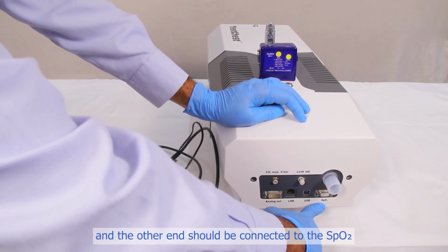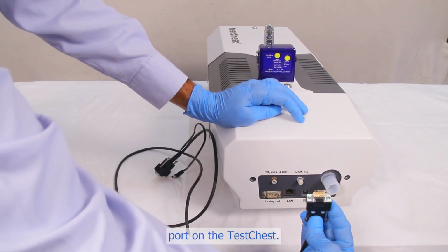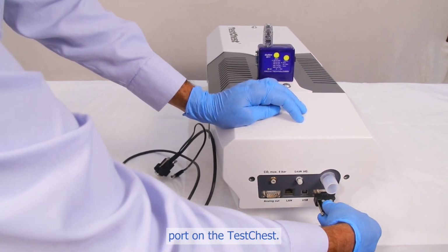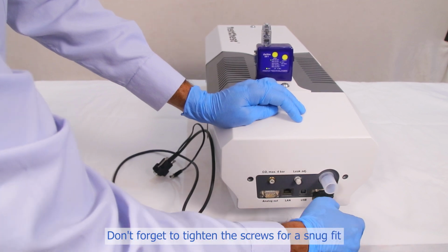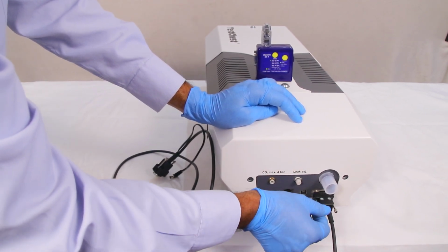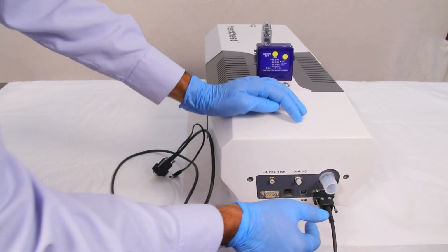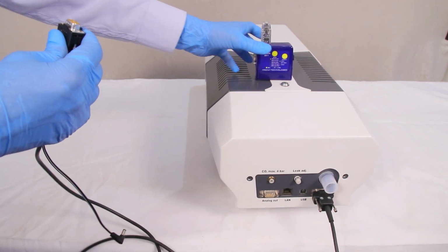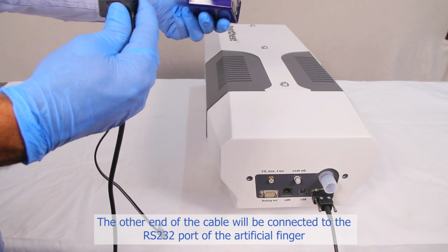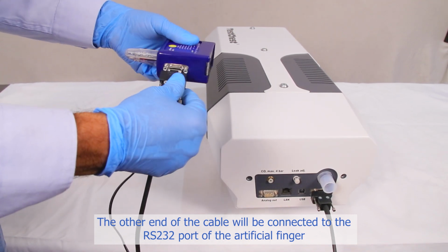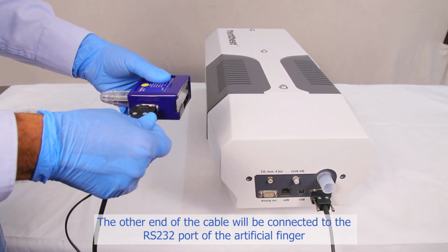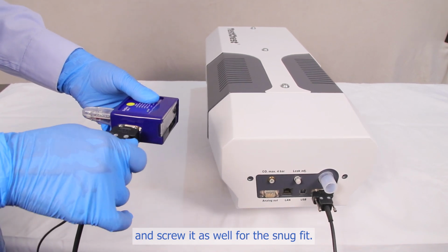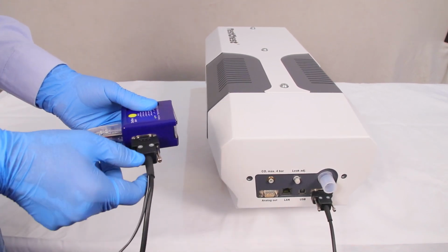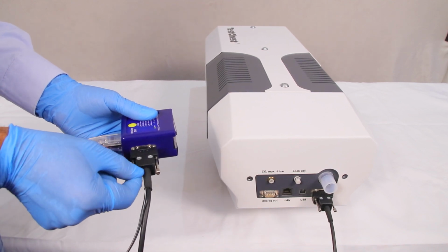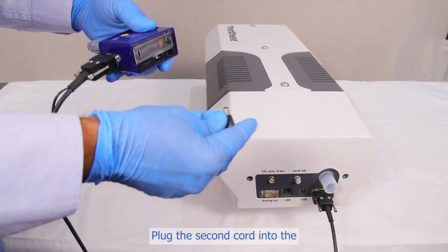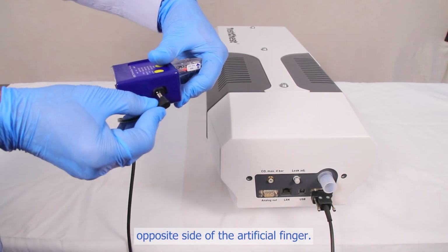And the other end should be connected to the SpO2 port on the TestChest. Don't forget to tighten the screws for a snug fit. The other end of the cable will be connected to the RS-232 port of the artificial finger, and screw it as well for the snug fit. Plug the second cord into the opposite side of the artificial finger.